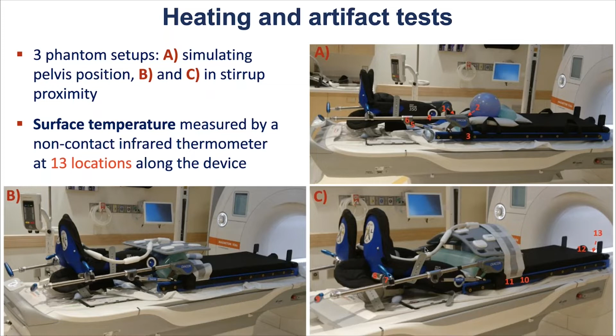In each of these tests, we were measuring also the temperature at points shown by the red numbers in the photos using a non-contact infrared thermometer. The results of our temperature measurements are shown in this graph for each location, and the material that was used in each location is shown at the top of the graph. The blue line shows the temperature measured at baseline, meaning before scanning, and the red, green, and yellow bars show the temperature after each test.